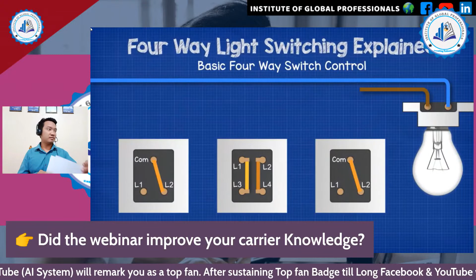Let's watch the basic types of wiring connection in four-way electrical wiring. The first circuit is the simplest method and easiest to understand, typically used for a new installation. We have two 3-terminal switches at either end, and an intermediate switch in the middle.